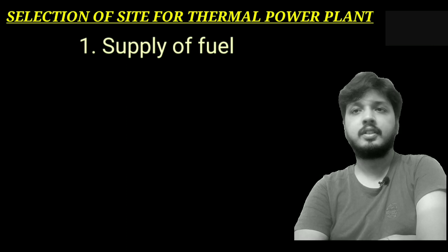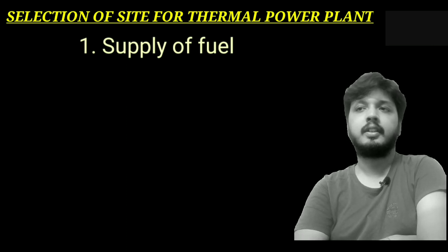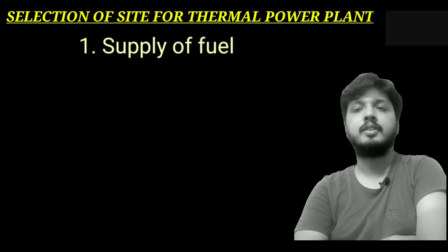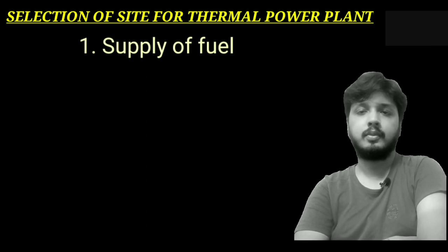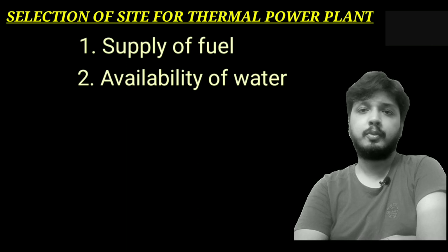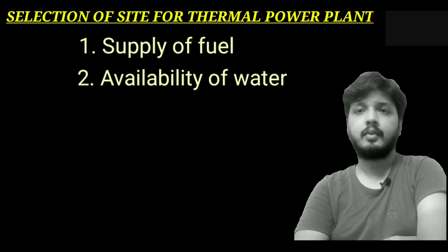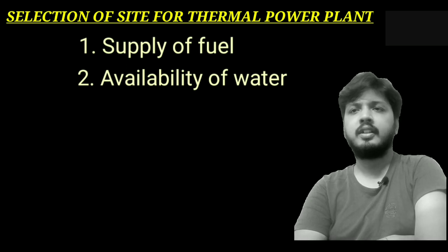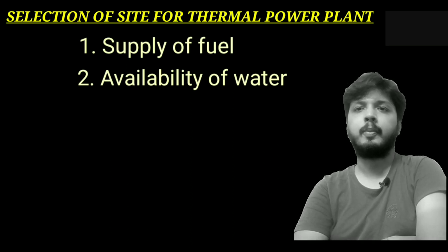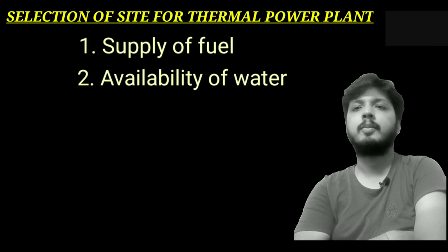However, if such a plant is to be installed at a place where coal is not available, then care should be taken that adequate facility exists for transportation of coal. Second, we have to remember availability of water. As huge amount of water is required for condenser, such a plant should be located on the bank of a river or near a canal to ensure continuous supply of water.